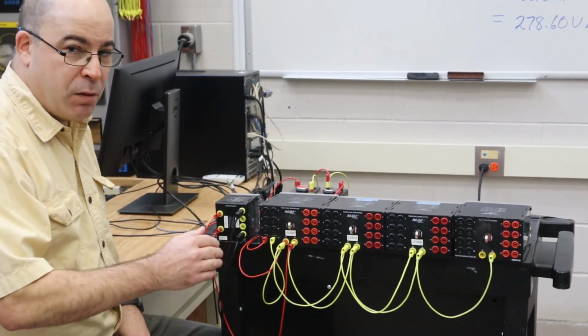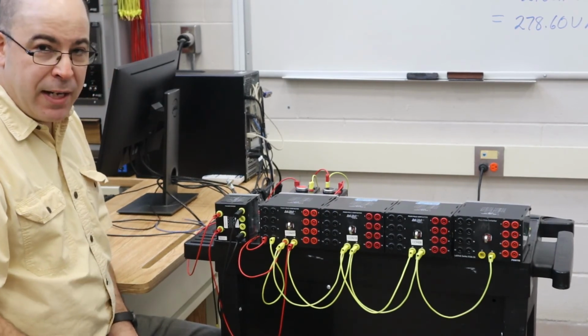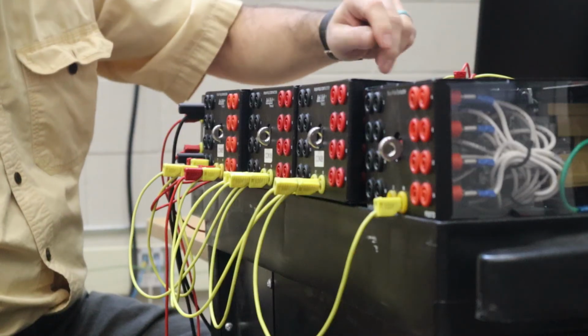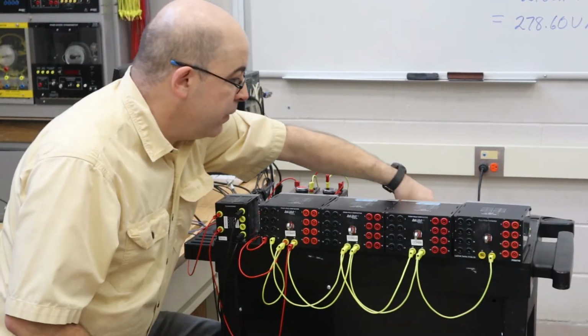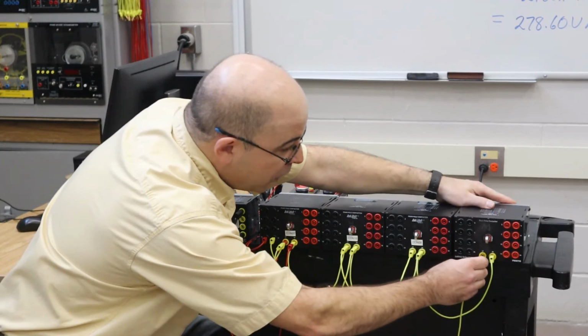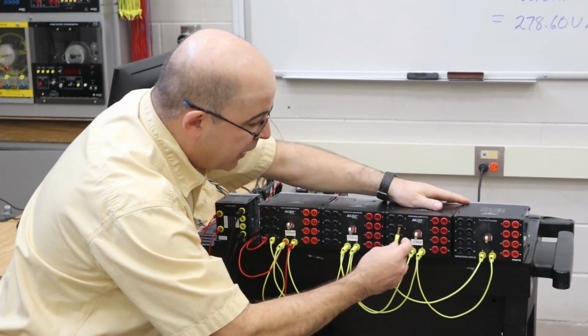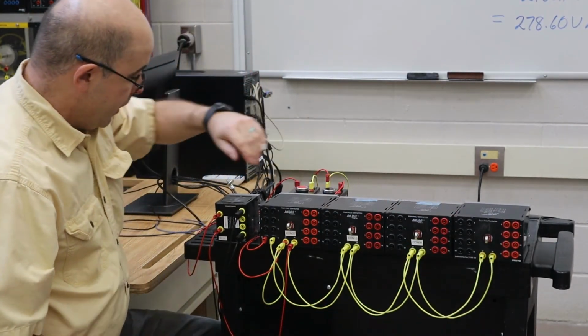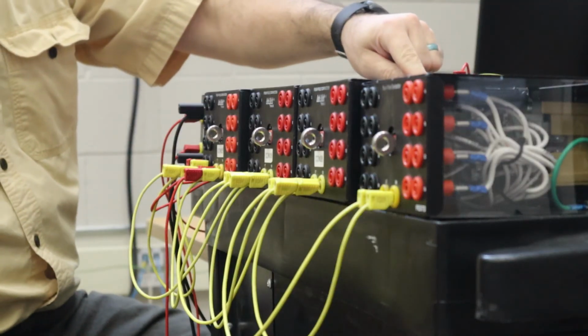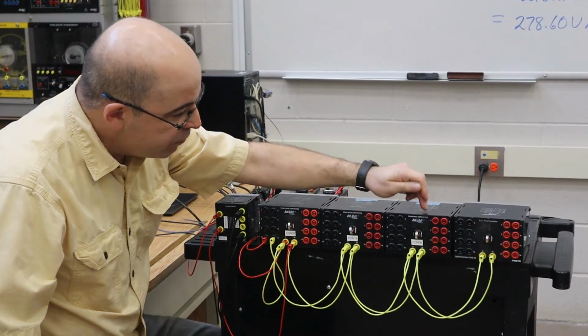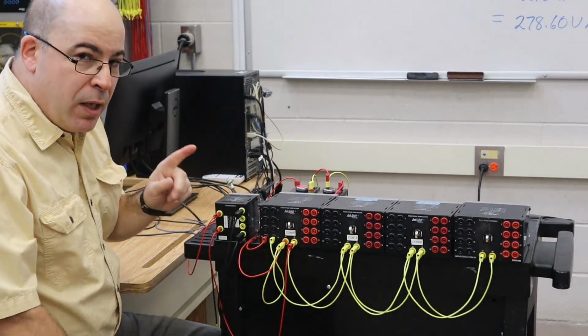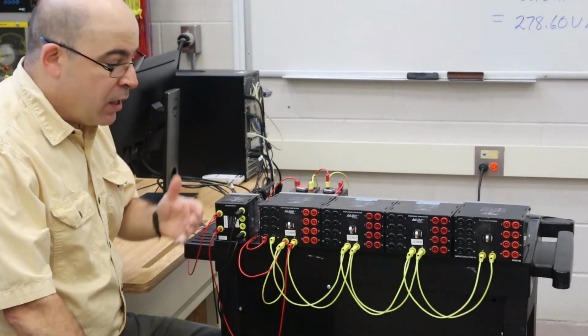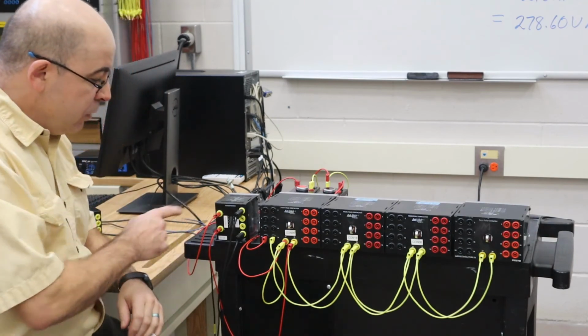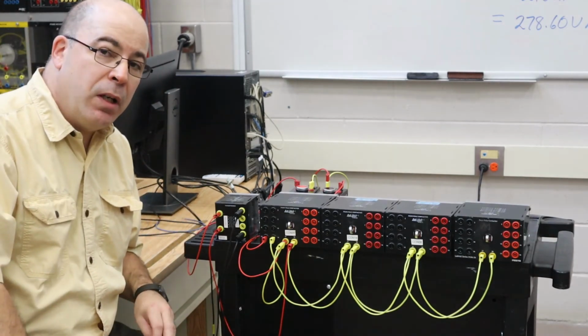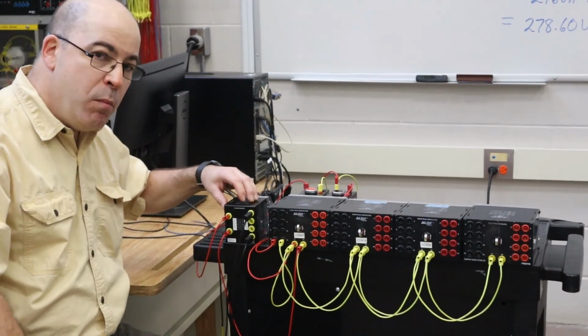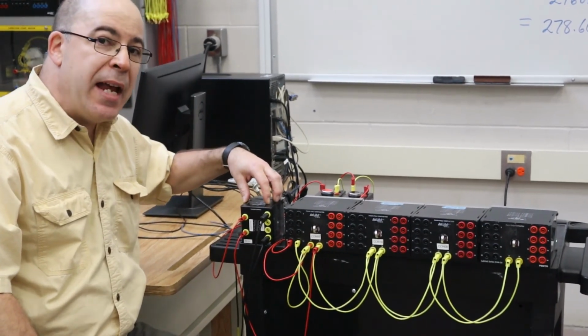Now, let's take it further. I've got a 4th relay. Let's try and energize it. So first, for safety's sake, we'll de-energize the control circuit, grab another lead, and we're going to add a 4th relay to the mix. And again, here it goes. 1, 2, 3, and 4. They're all working, but there's a little bit more noise or humming coming from the relays. Now, while the transformer is providing us with enough power, it could be that we're actually drawing a little bit more current than the transformer was ever designed to deliver.